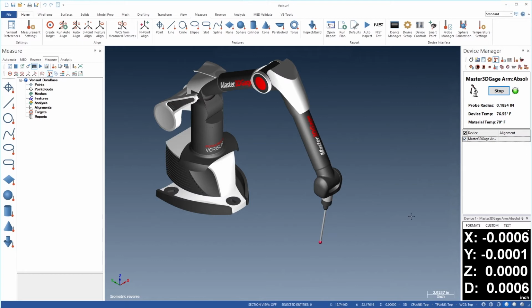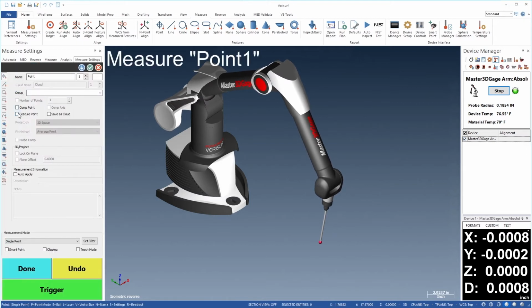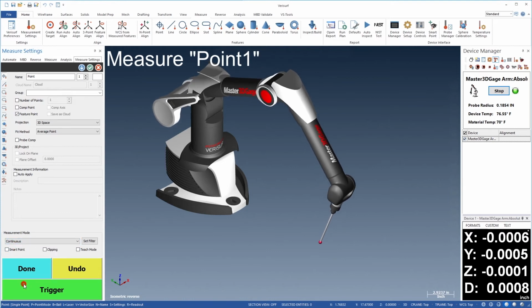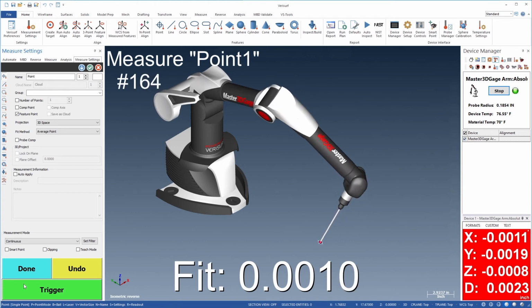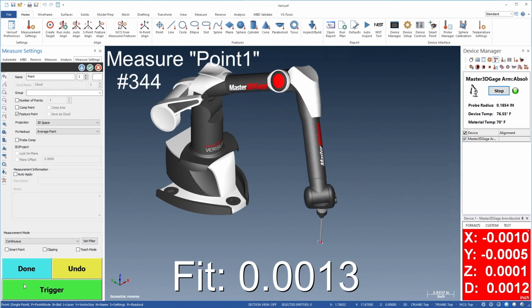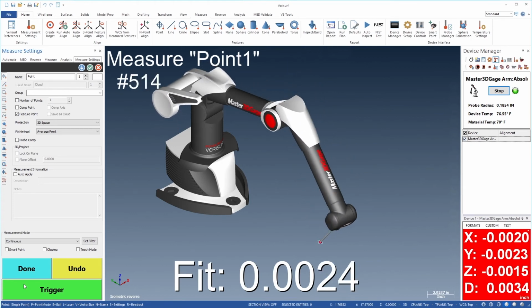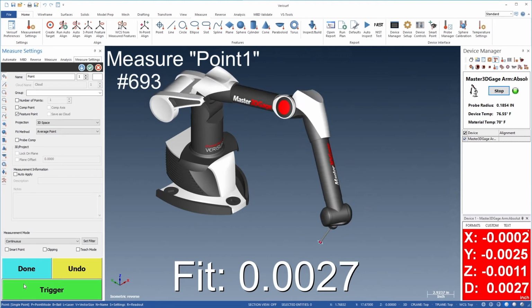arm. We'll choose Point Mode and enable Feature Point, leaving Fit Method set to Average Point. We'll then choose Continuous Measurement Mode to capture points at the maximum data rate. With the probe still in the nest, we'll trigger the device and articulate the arm as in the initial test. During measurement, the fit error from the running average is displayed at the bottom of the screen.